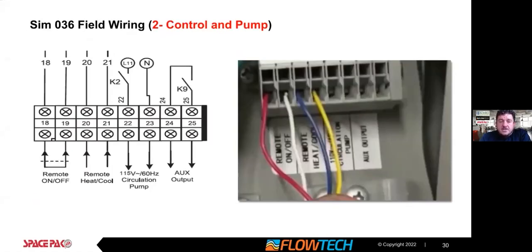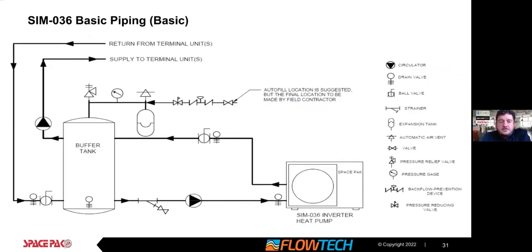And just keeping it simple, this is the wiring on the side of the unit for both the 3-ton and the 5-ton. And I've had customers, in a very simple way, turning it on and off with a dry contact, a closed contact on an end switch, and they have it either jumpered or they put a heat cool toggle switch in the mechanical room, set the water temperature, and away you go. So these are the wiring connections on the side of the units, and it's very simple to do. You'll see this as well in future slides.